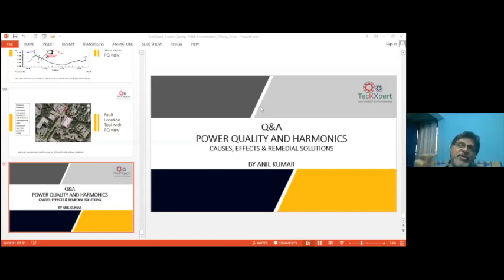But yes, as I said before, if you have a grid level or substation level, and you put multiple PQ meters and do time synchronizing by using GPS syncing, then you can always look at the relationship of flow, or the phase angle, at multiple nodes and come to conclusions on which direction the harmonic power flow happens. Yes, so I hope I answered this question.